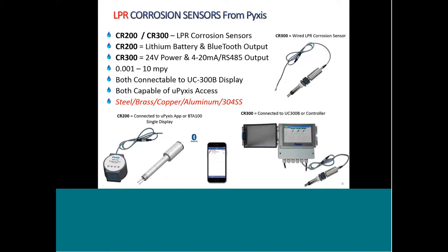The other thing that's an advantage is we've designed it so that it's interchangeable with any conventional electrodes. We do offer 5 different metallurgies for this technology: untreated steel, brass, copper, aluminum 6061, and 304 stainless. In essence, the other advantage is the level of detection of the device is 0.001 mils per year, and it offers both general and localized pitting corrosion as the output. When wired, it will be wired as two 4 to 20 milliamp analog output signals if you're wiring it in that format. If you're wiring it in digital format through Modbus, you just connect the Modbus connectivity, digital diagnostics of the probe.